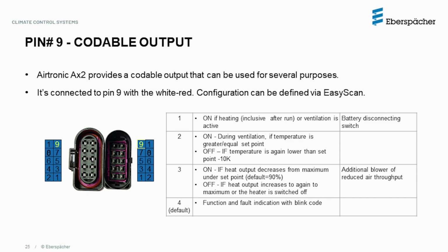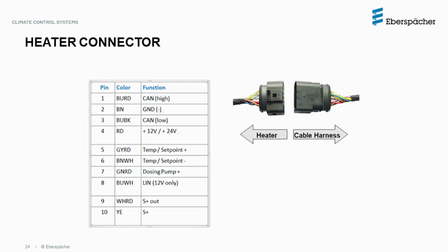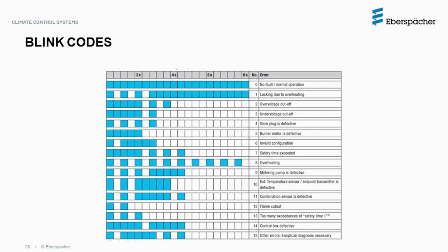This would include when the heater operates in heating or ventilation mode, or when the heater operates in ventilation mode and the ambient temperature does not drop 10 degrees Kelvin or more, or when the heat output does not drop more than 10% of the maximum output. Pin 10 is used to receive an input signal, either 12 volts or 24 volts from the analog controller, and is used to activate the heater. This activation signal bypasses the CAN communication channel on the heater. The Airtronic 2 heater manual will outline the different blink codes available with their description and instructions. Blink codes are not as comprehensive as the regular diagnostic fault codes.